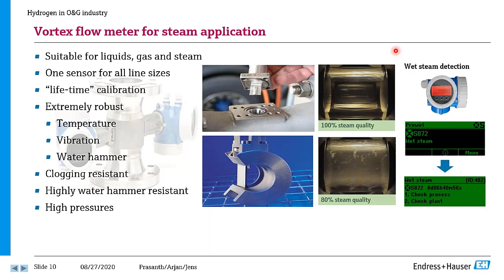Some other features on our Vortex flow meter: extremely robust against temperature, vibration, water hammer. Water hammer is a constant feature when we talk about steam application, and we have devices which can cater for high pressure application. What you see on the right side on this slide is wet steam detection, quality of steam. With our Vortex flow meter up to meter size 4-inch, we can do wet steam detection and also give you a message in terms of the quality of the steam you have in your pipeline.